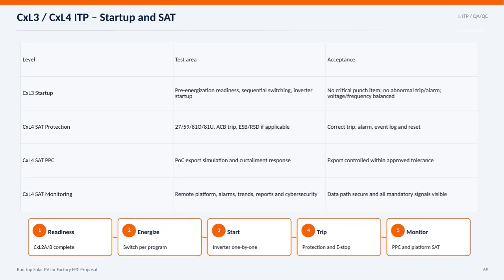Here we have the key stages involved in the CXL3 and CXL4 ITP processes for startup and SAT, specifically for the rooftop solar PV EPC proposal. First, during the CXL3 startup phase, we focus on pre-energization readiness, sequential switching, and inverter startup. The goal here is to ensure there are no critical punch items and no abnormal trips or alarms, while maintaining voltage and frequency balance. Moving to CXL4 SAT protection, we test critical protection functions like relay tripping and alarms to verify correct operation, event logging, and reset capability.